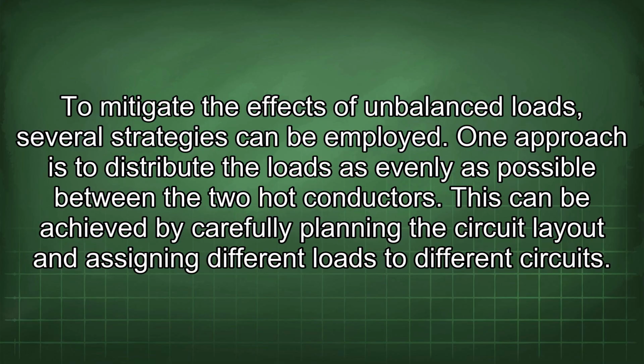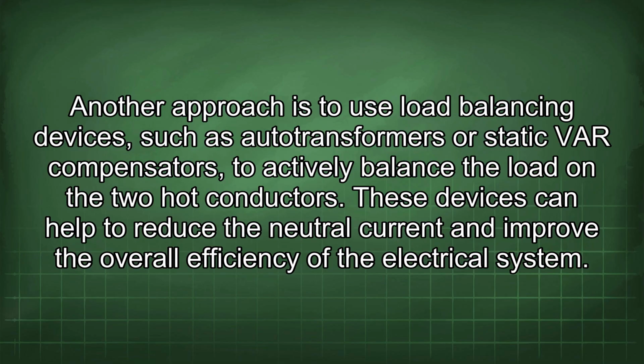To mitigate the effects of unbalanced loads, several strategies can be employed. One approach is to distribute the loads as evenly as possible between the 2 hot conductors. This can be achieved by carefully planning the circuit layout and assigning different loads to different circuits. Another approach is to use load balancing devices, such as autotransformers or static VAR compensators, to actively balance the load on the 2 hot conductors. These devices can help to reduce the neutral current and improve the overall efficiency of the electrical system.